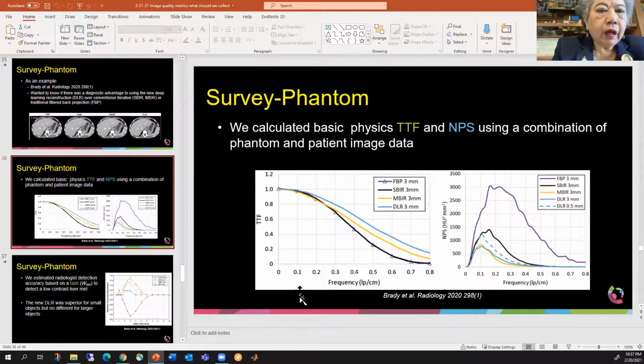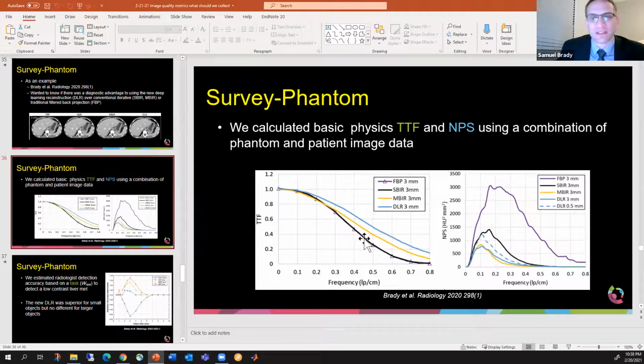Thanks, Sam. This is Chirapon. I'd like to ask you, when we do the survey or research for the whole country, if we use different kinds of phantoms, can we combine the data, or do we need to separate them? You can, it depends on the task. For example, if you have the CATPHAN phantom and the ACR phantom, 2 different phantoms, you can still calculate the same MTF. You can still do these 2 exact same calculations.